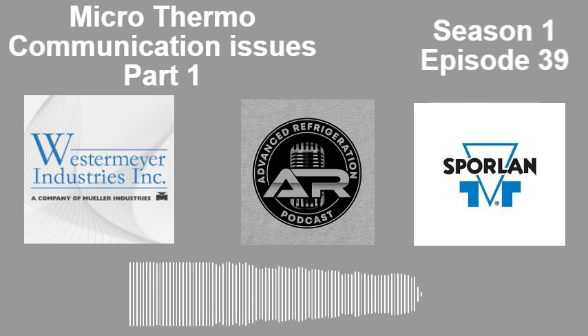And what Brett mentioned, you go to this wink button. Okay, you click it once, and what that's going to do, it's going to be the opposite. Our normal blink is 1 second on, 6 seconds off, 1 second on, 6 seconds off. When I hit wink, that board's going to be 6 seconds on, 1 second off, 6 seconds on, 1 second off. So you can look at 3 or 4 boards next to each other, and now I've identified the board that I'm looking for because I've used the wink function. Okay. Now, my network variables, I can see them. Those are the NVIs and NVOs that I was talking about.